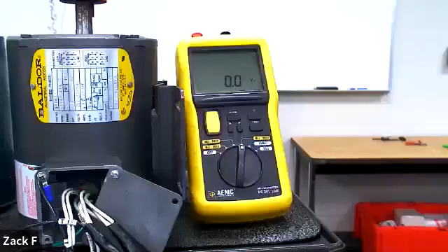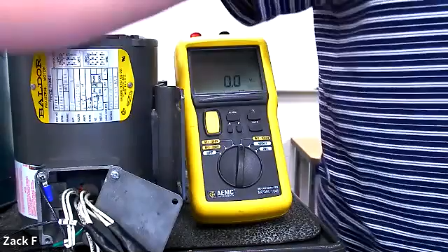It depends on how you want to check it. If you think the fault is going to ground, you could use this to check. I could also use this to check against each winding. In that case, I'd want to isolate this winding from all the other ones. But if I wanted to check, let's say I could put one lead on 2 and one lead on 8 to make sure this isn't touching or rubbing against these 3 somehow, some way. You can check them against each other too, they're not just for ground faults. But a lot of times something that bad, if it's shorted together, will show up with your meter.